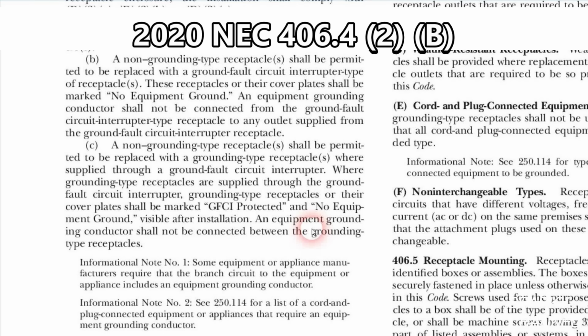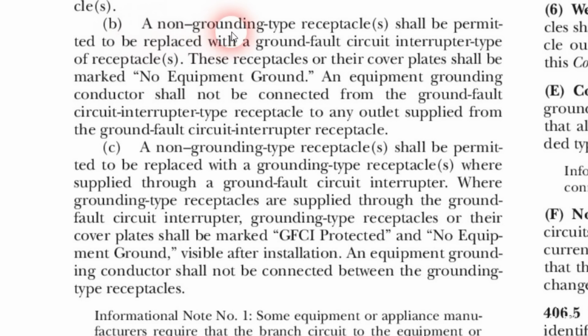Here we are at NEC code 406.4(2)(B). A non-grounding type receptacle shall be permitted to be replaced with a ground fault circuit interrupter type of receptacle. These receptacles or their cover plates shall be marked no equipment ground. An equipment grounding conductor shall not be connected from the ground fault circuit interrupter type receptacle to any outlet supplied from the ground fault circuit interrupter receptacle.